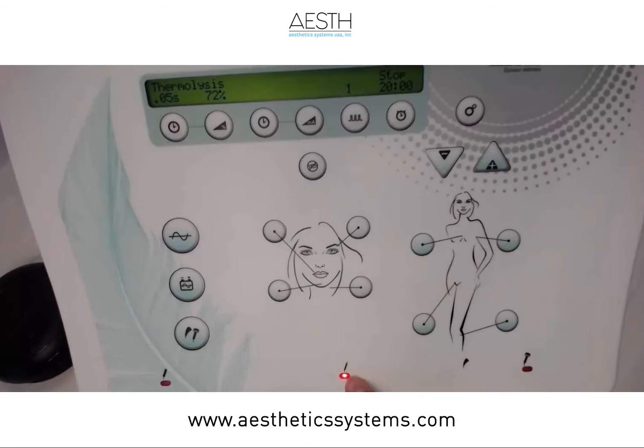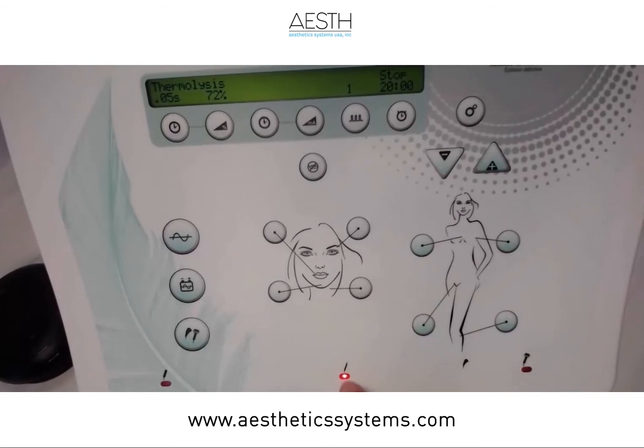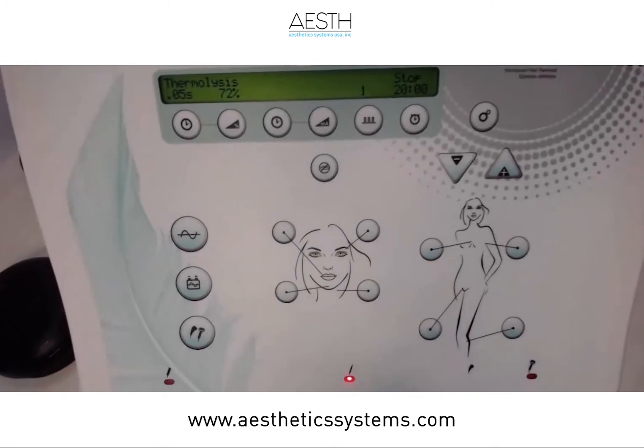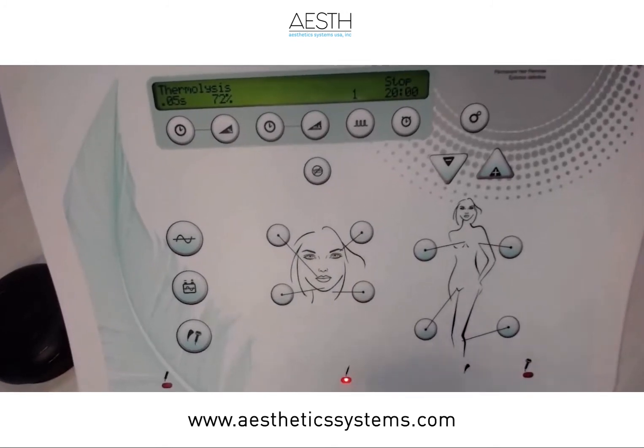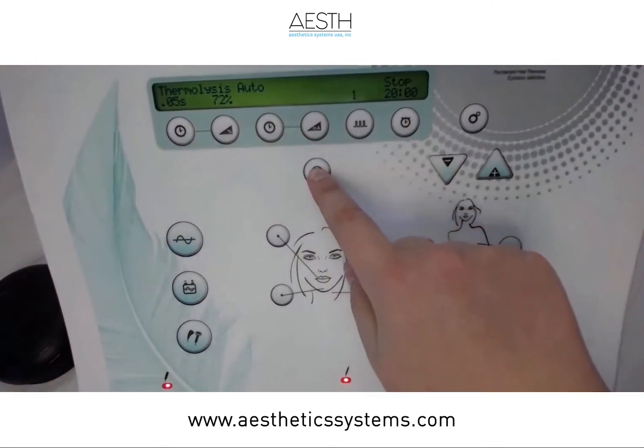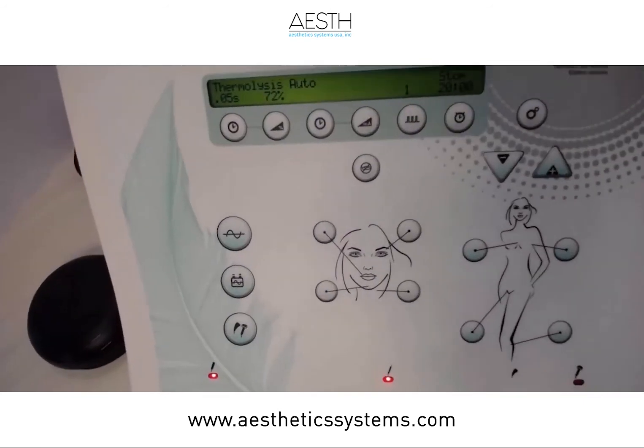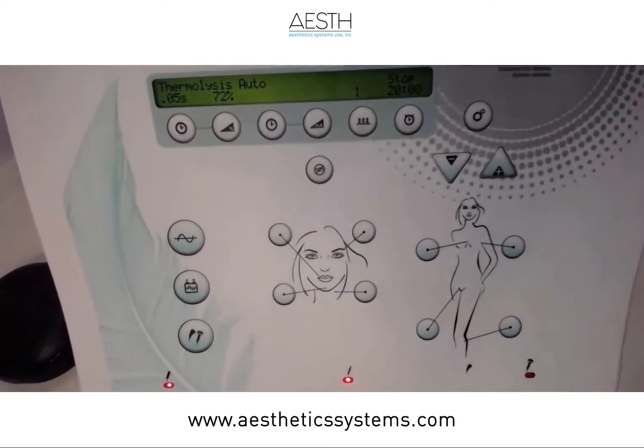Normally, because I'm in treatment mode, the light that's lit is the one on top of my probe holder, where it connects down here. When doing thermolysis, there's normally no ground required. But if I work auto mode, this light lights up on top of where my red connector is. The red connector gets plugged in there—that is the ground, the thing the client has to hold.